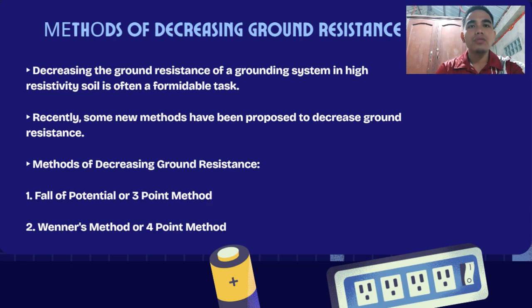So next is the Wenner method, or four-point method. It's another simple way to measure how well the soil conducts electricity, mainly used before installing a grounding system. You place four metal rods in a straight line, equally spaced. Rod 1, current in; rod 2, voltage measurement; rod 3, voltage measurement; and rod 4, current out. All rods are spaced evenly, 1 meter apart or 2 meters apart. How does it work? A tester sends current through the outer rods, 1 and 4. Then it measures voltage between the inner rods, 2 and 3. Then it calculates the soil resistivity.